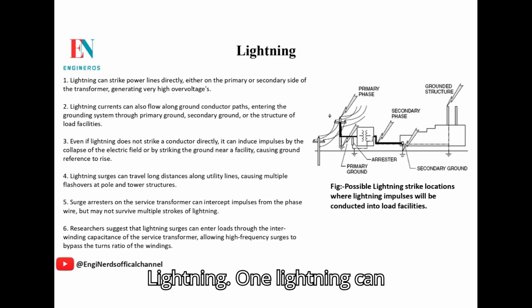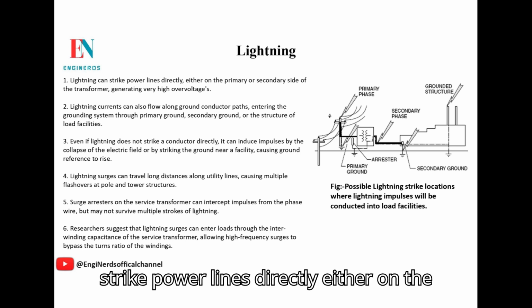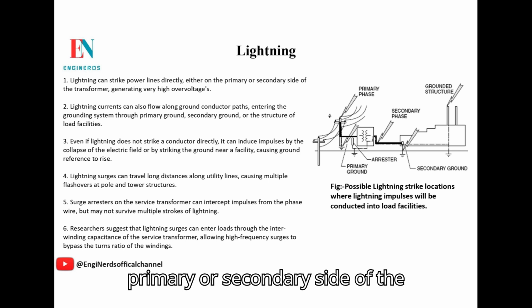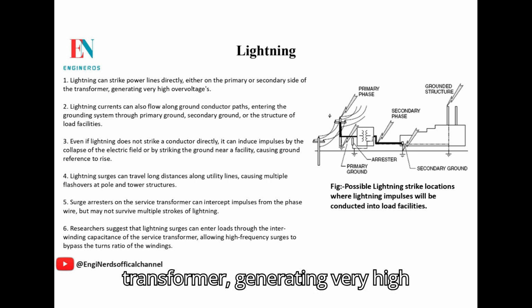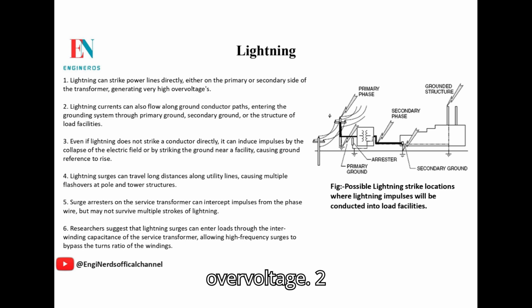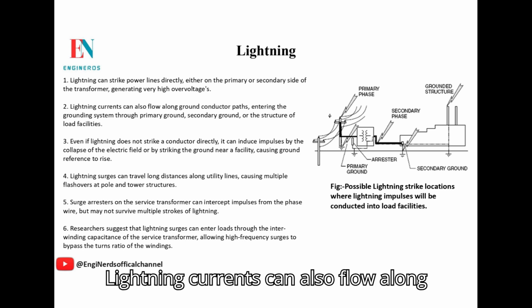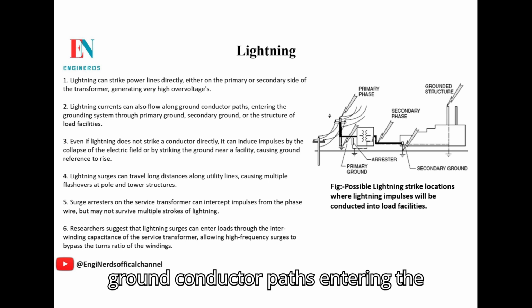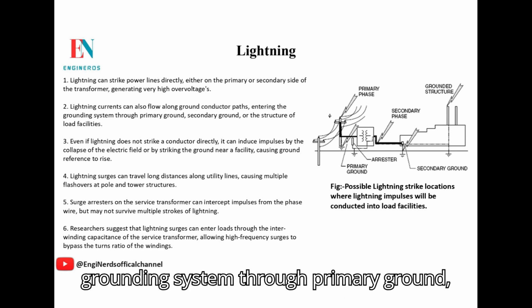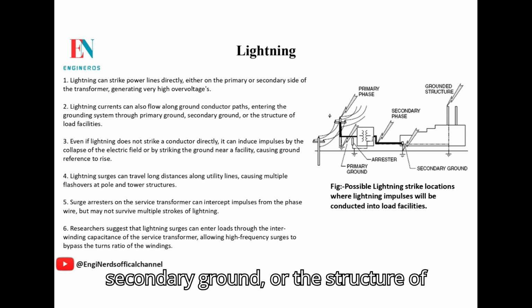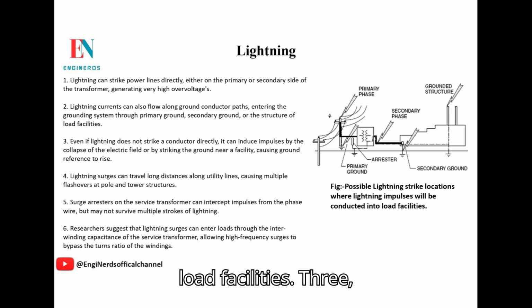Lightning. 1. Lightning can strike power lines directly, either on the primary or secondary side of the transformer, generating very high overvoltages. 2. Lightning currents can also flow along ground conductor paths, entering the grounding system through primary ground, secondary ground, or the structure of load facilities.